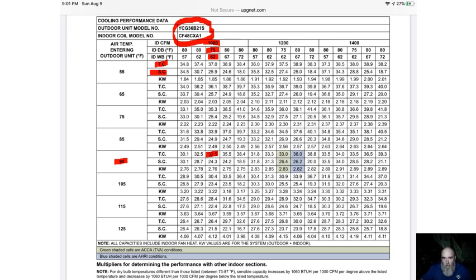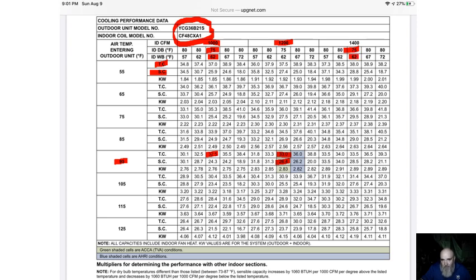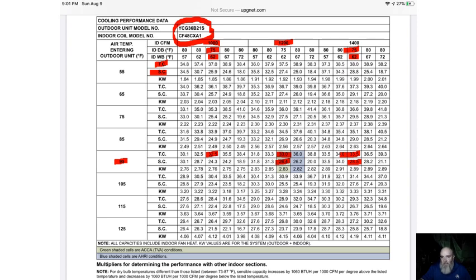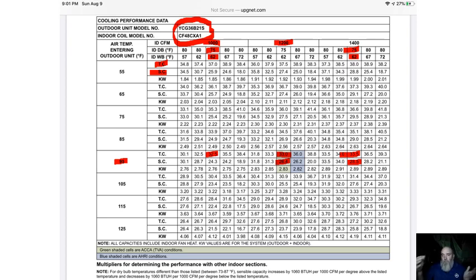If we go up to the 1,200 CFM line, we see our sensible capacity increases slightly and our total capacity has increased. The bigger airflow at 75 degrees, 50% relative humidity, we gained another 500 BTUs or so for our total and sensible capacity. If you calculate your latent capacity, you would see the smallest latent capacity at the highest airflow. Every time we step down in airflow, we will see our total drop, we will see our sensible drop, and we would see our latent increase as we move to the left and slow it down.